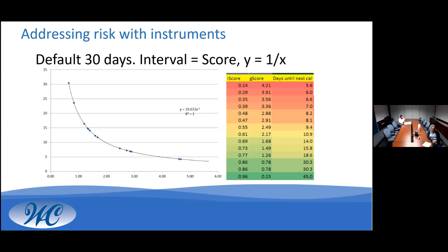of results. Initially, we tried using a static linear correlation between calibration score and a set interval between calibrations. However, it was found that with a linear correlation, the instrument's calibration interval wasn't tightened quick enough, resulting in instruments still being thrown out of calibration. This showed that a linear correlation would not provide the desired response. If you want to visualize this, just draw a straight line from the very top of that curve to the very bottom. If you notice, as the score goes along, the calibration interval doesn't decrease as quickly.